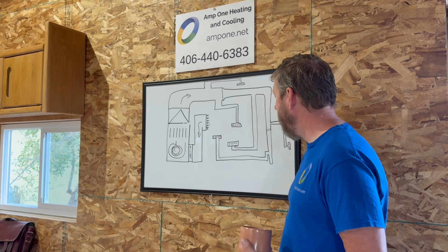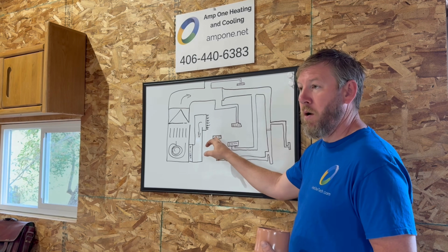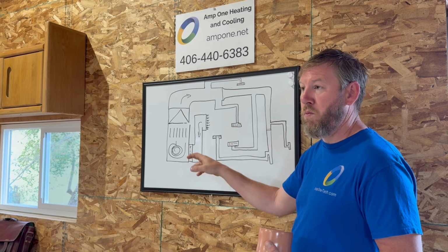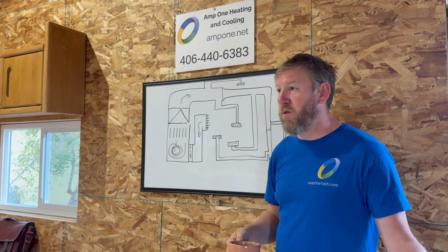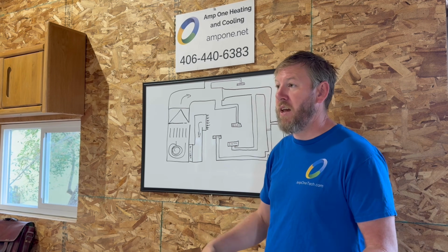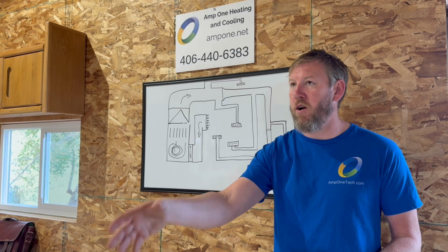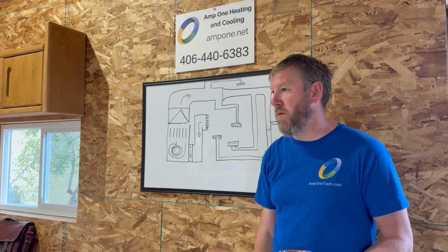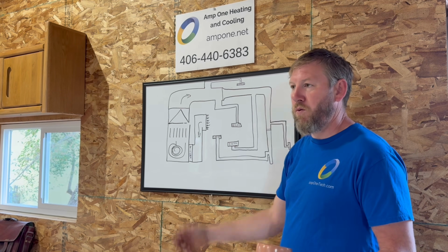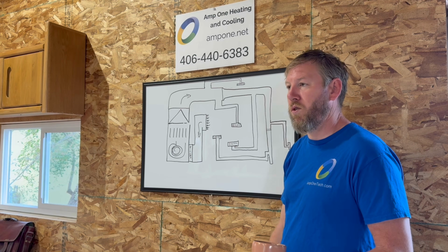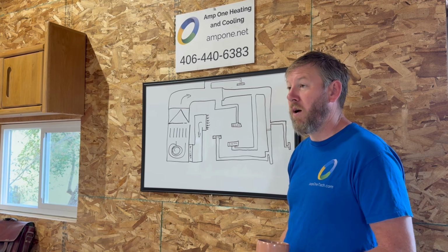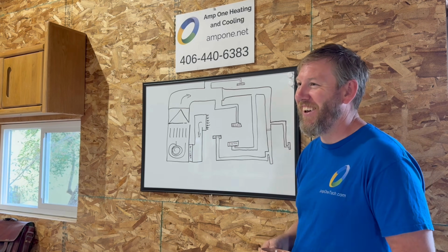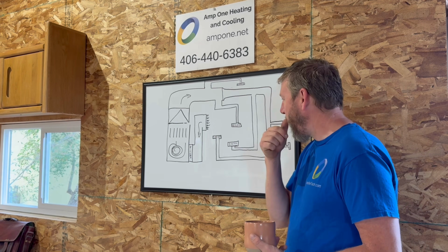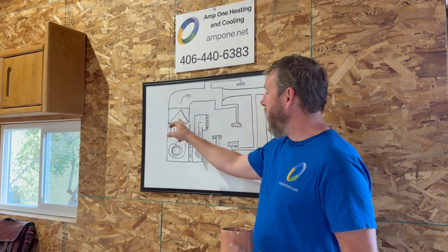Take the filter out. Each one of these vents is going to pump out a certain amount of CFM for the room. That's why in certain rooms we run a 7, an 8, because we're trying to get that amount of air to the size of room. Mm-hmm. And there are formulas for all of that stuff. Of course, do I know it off the top of my head? I should, but I don't. Geez, that sounds like a lot of math. And then each furnace... What's that?